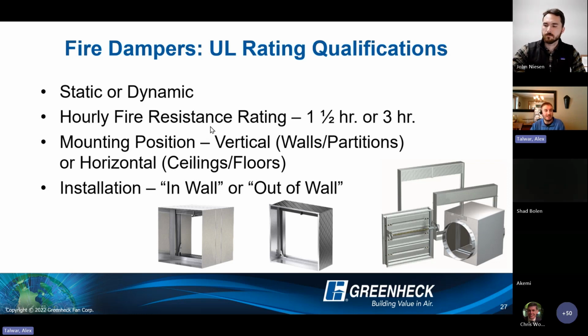We do have specialized products that allow you to get the damper itself, the damper frame, actually offset from the wall up to 7 or 8.5 inches, I believe. But those are specialized products. They come wrapped with a thermal blanket. They're tested separately, so that is something that you'll need to know.